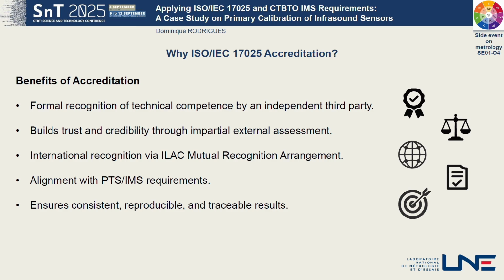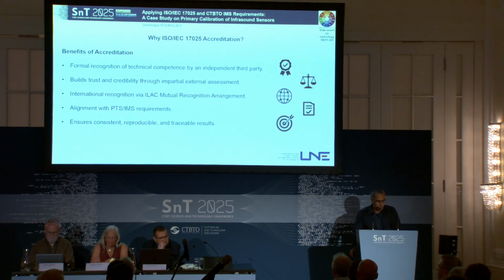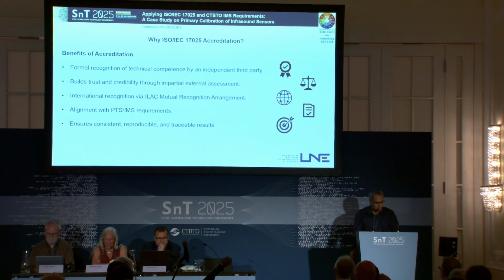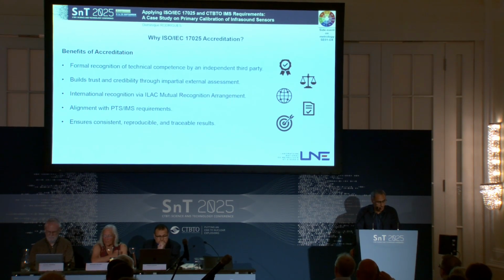Okay, so first question, why target such an accreditation according to this standard? Such accreditation is of course more than just meeting a standard. It's a formal recognition of competence by an independent third-party accreditation body, and I believe this independent supervision is very important to build trust and credibility. Thanks to the ILAC mutual recognition arrangement, the accreditation is recognized internationally, so calibration certificates can be accepted in almost all countries in the world without the need to retest the equipment. It also means a direct alignment with the PTS IMS requirements, and finally it ensures that the results are consistent, reproducible, and, very importantly, fully traceable to the international system of units.